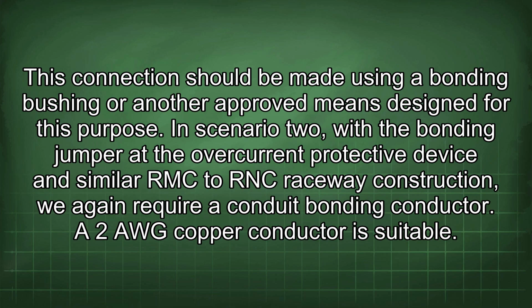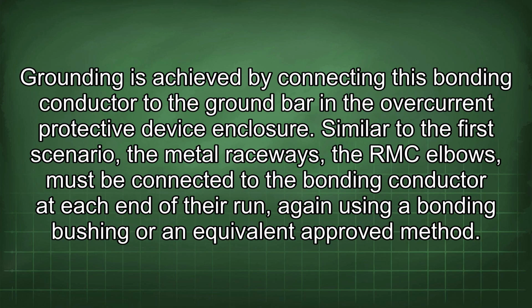In Scenario 2, with the bonding jumper at the overcurrent protective device and similar RMC to RNC raceway construction, we again require a conduit bonding conductor. A 2 AWG copper conductor is suitable. Grounding is achieved by connecting this bonding conductor to the ground bar in the overcurrent protective device enclosure. Similar to the first scenario, the metal raceways, the RMC elbows, must be connected to the bonding conductor at each end of their run, again using a bonding bushing or an equivalent approved method.